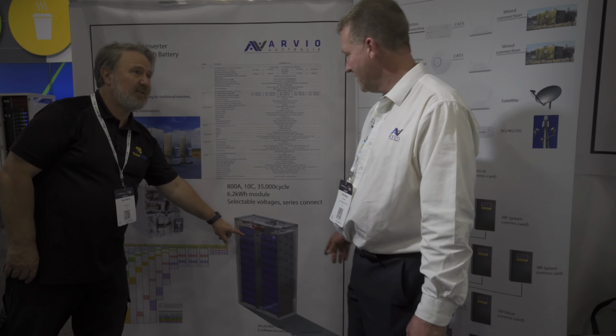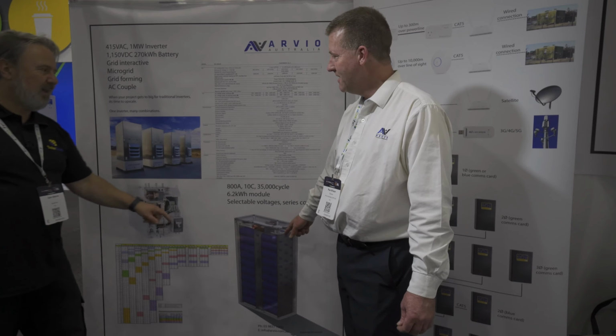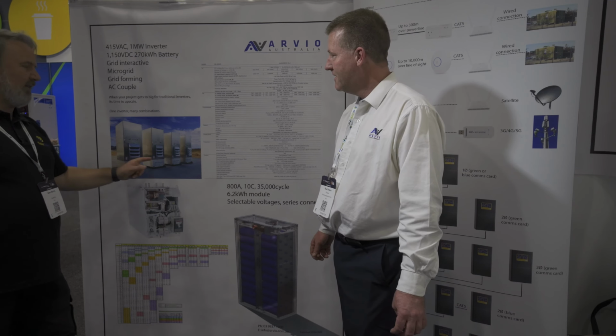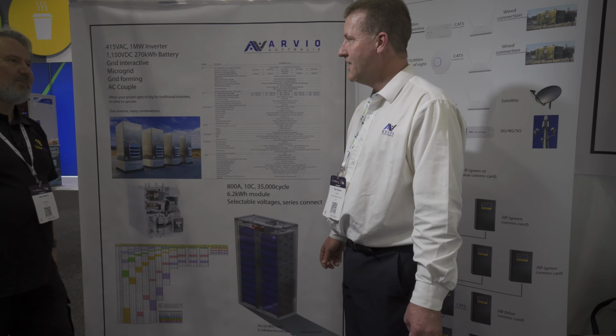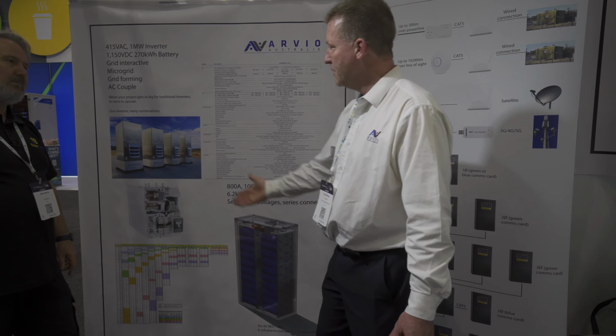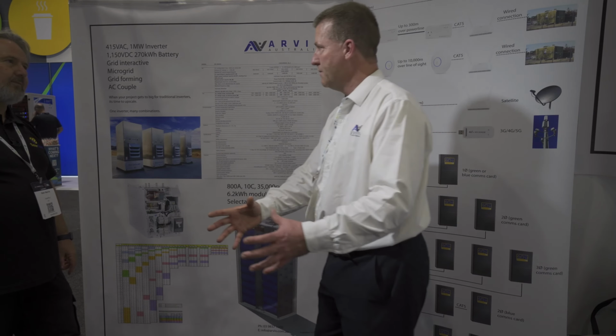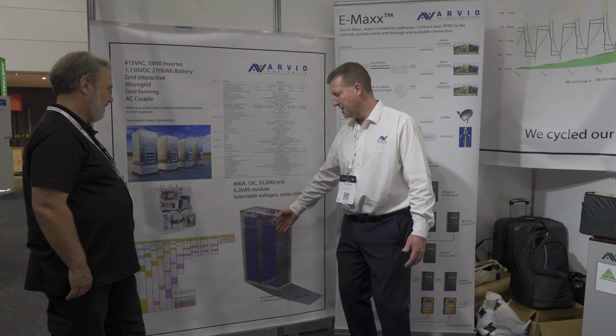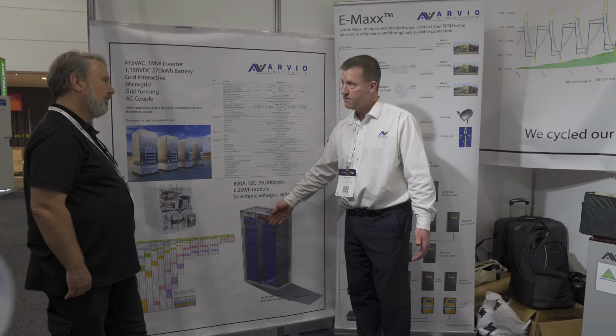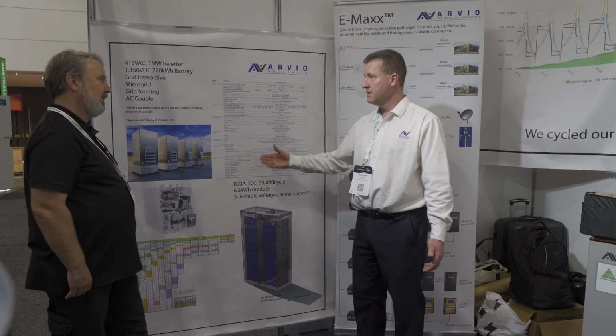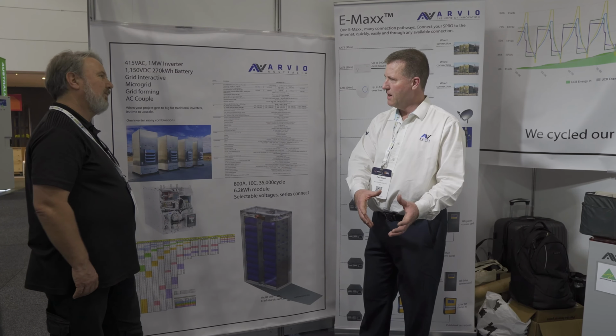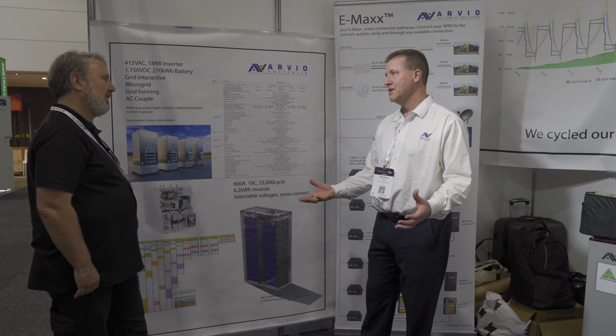So you're taking something that starts off as about a 45 amp hour cell and building megawatt scale storage with megawatt power. That's right. So you could take a shipping container, put in one of these, put a transformer in the end of it, and then put in, say, maybe 400 kilowatt hours of these, and you have a 1 megawatt AC output with 300 kilowatt hours of storage, so say 20 minutes of burst energy.